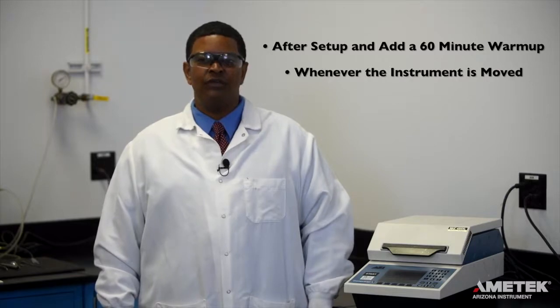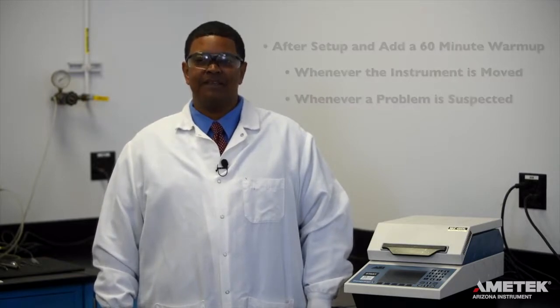Before you can begin to run samples on your Max 4000 XL or Max 4000, you will need to perform a balance span calibration and a weight test. Span calibration should be performed after setup and a 60-minute warm-up, or whenever the instrument is moved or whenever a problem is suspected.